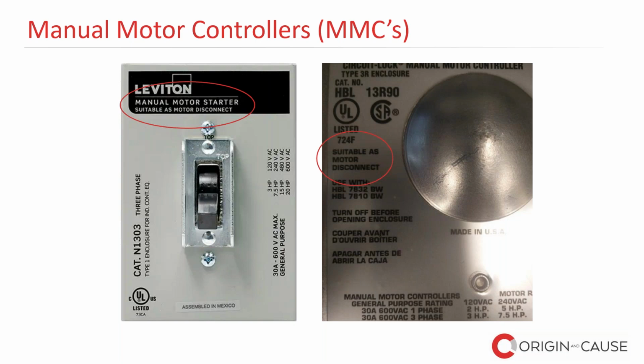But what people have started doing is using it as a disconnecting means. Now, the Ontario Electrical Safety Code defines a disconnecting means as something that's certified and approved to be used as a disconnect, such that you can maintain equipment downstream, and you can remove equipment, you can replace equipment. The manual motor controllers are not necessarily for that, unless, like in these two examples, it actually tells you that you may use it as such, and it says right on it that it is suitable as a motor disconnect.